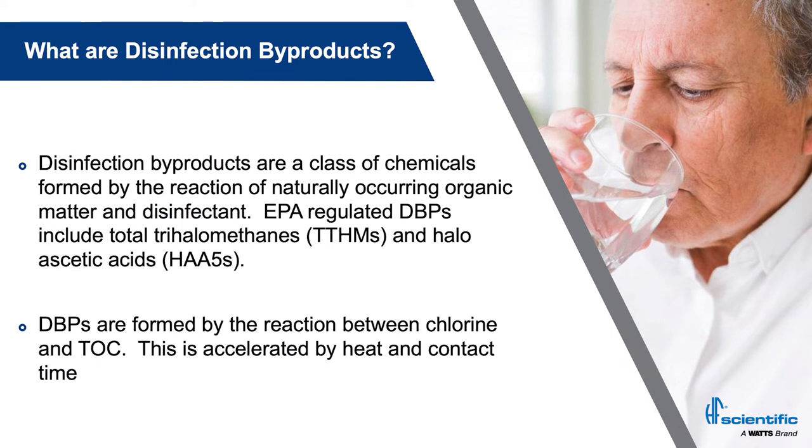So what are disinfection byproducts? Disinfection byproducts are a class of chemical formed by the reaction of a disinfectant with bromide or naturally occurring organic matter, such as decaying vegetation, fish, or other organisms present in the source water. We often refer to the precursors of disinfection byproducts as TOC. The EPA issued the Stage 1 and Stage 2 disinfectant byproduct rules in the late 90s and early 2000s, and we're still seeing plants make changes to meet these rules. The current regulated DBPs are haloacetic acids and total trihalomethanes — TTHMs and HAA5s. The reaction of chlorine with TOC in the source water is driven mainly by time and heat.